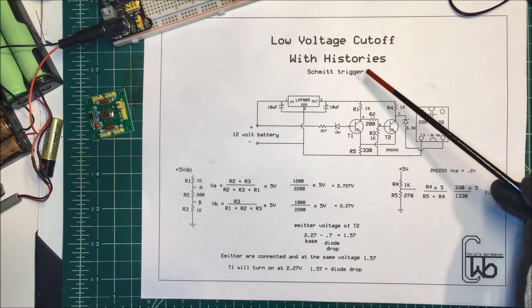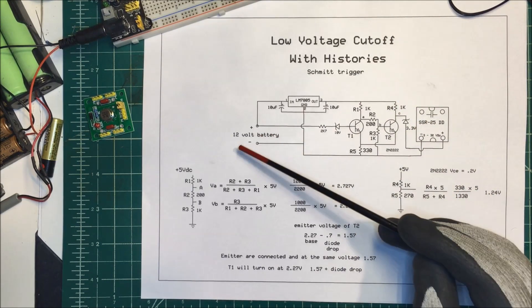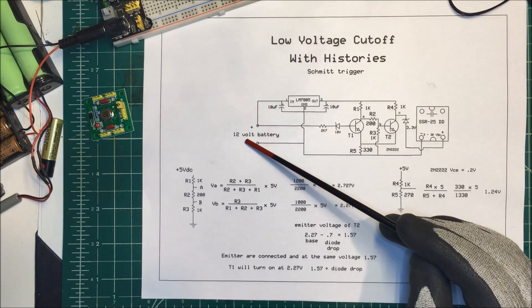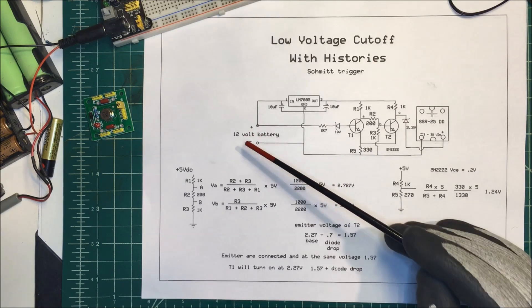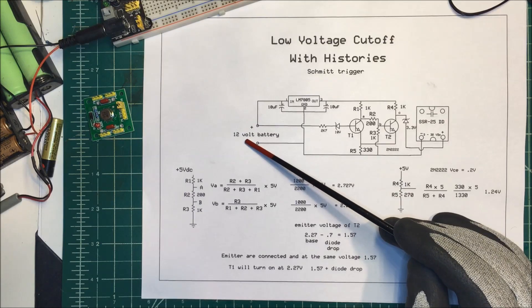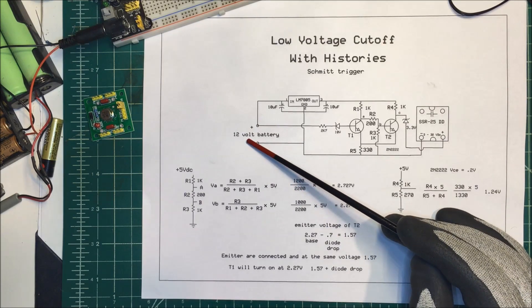Let's talk about low voltage cutoff with hysteresis. I've got a 12 volt battery and I want to be able to disconnect the load when the voltage drops down to say 10.5 volts and then be able to automatically turn the load back on if the voltage rises up to say a little bit over 11 volts.